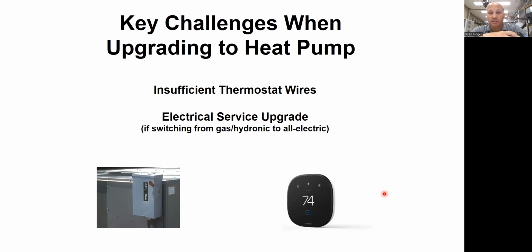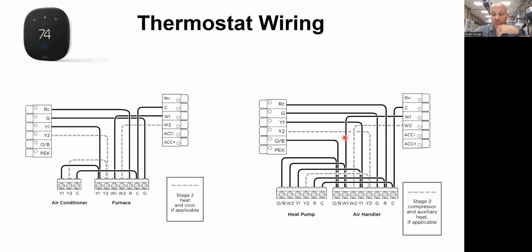So I will probably need an electrical upgrade from switching, like it says in the notes here, from a gas-fired system, or even a hydronic or steam system, hot water or steam system, to an all-electric system. I'm probably going to need more electrical power. And by probably, I mean I am, for sure. The thermostat wiring is the other thing that might have to change, and usually it will.